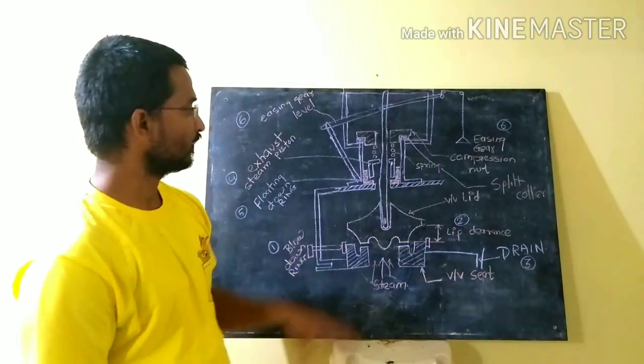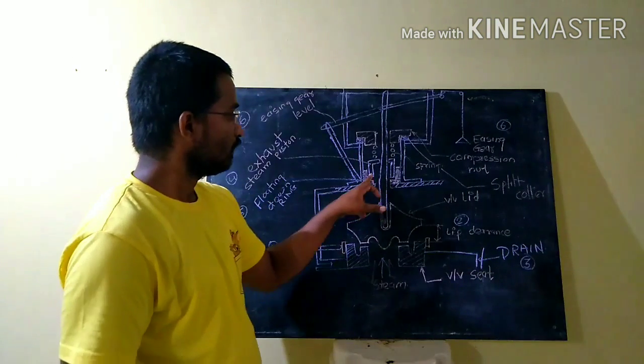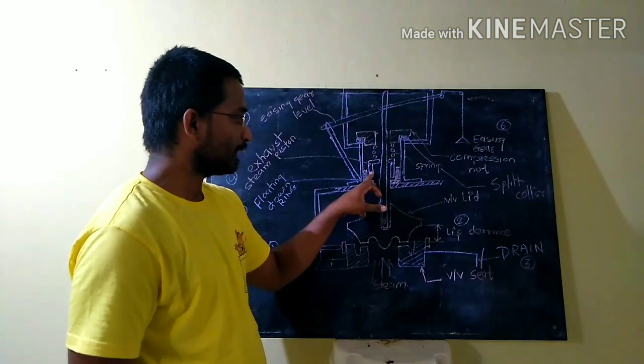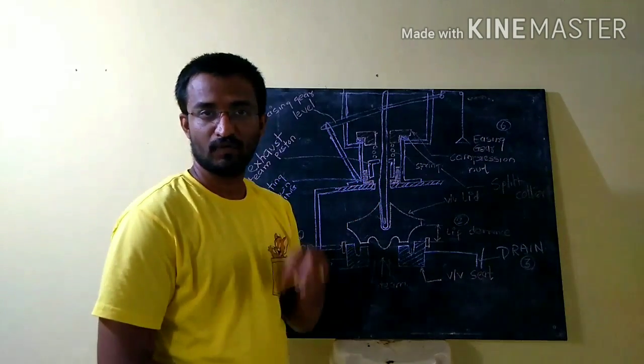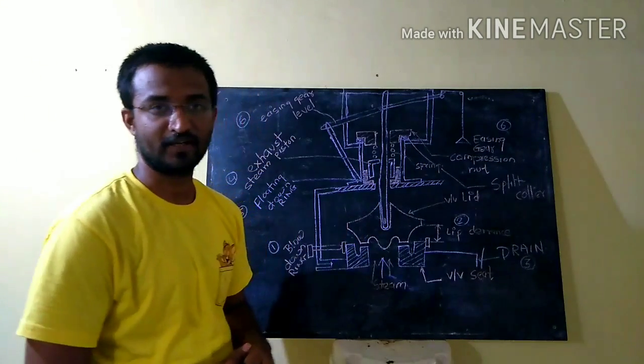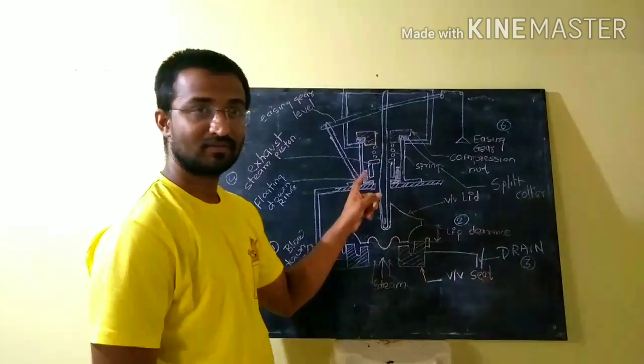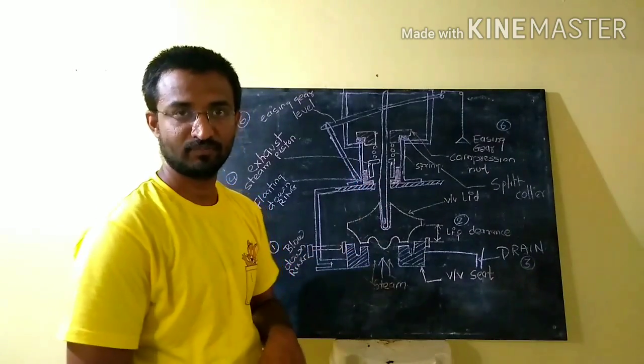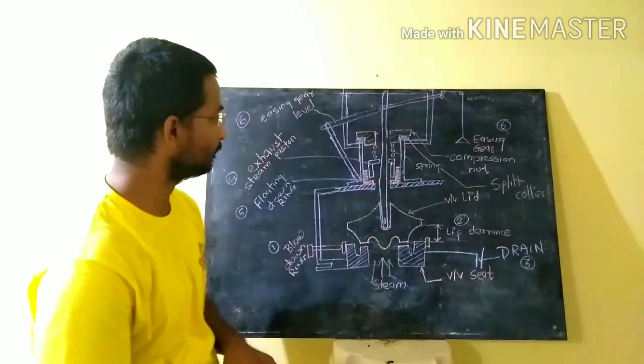Once you check the drain and assemble all the things, check whether the piston is free to rotate or free to move inside the floating ring. This is very important, that the piston has not stuck anywhere. It is free to move in the floating ring.